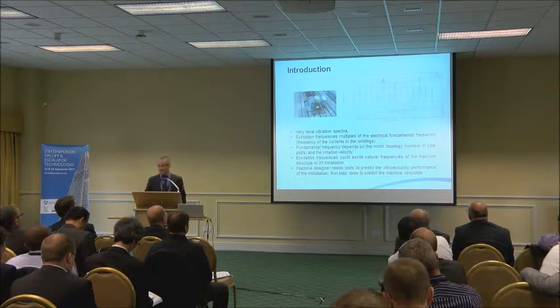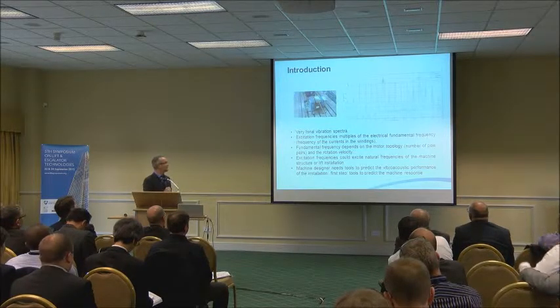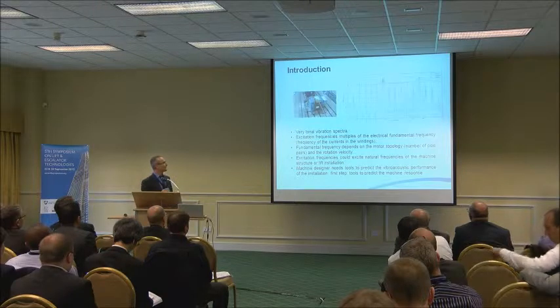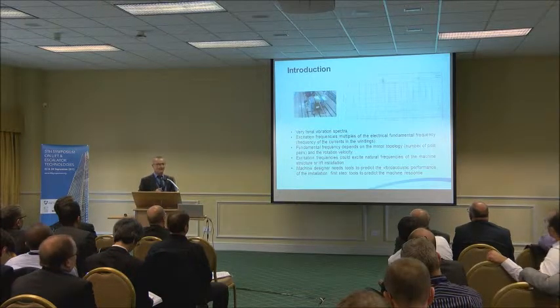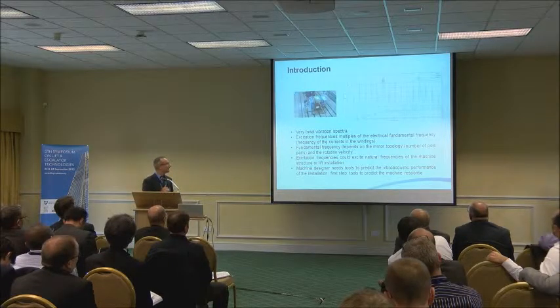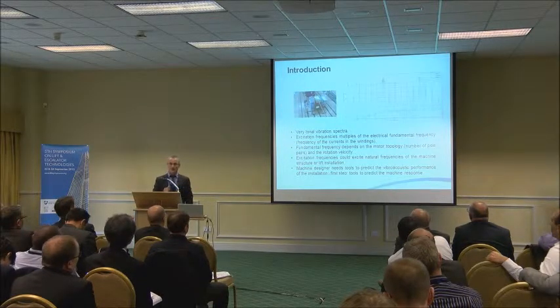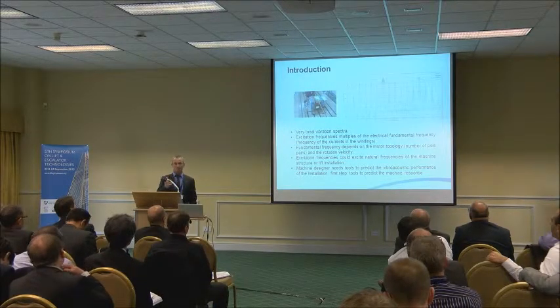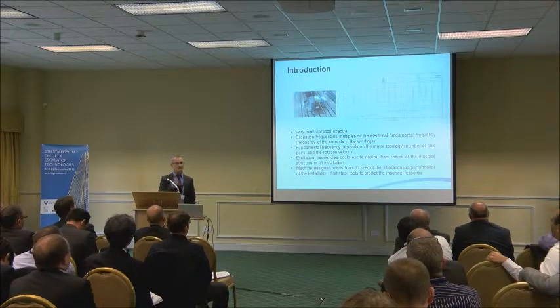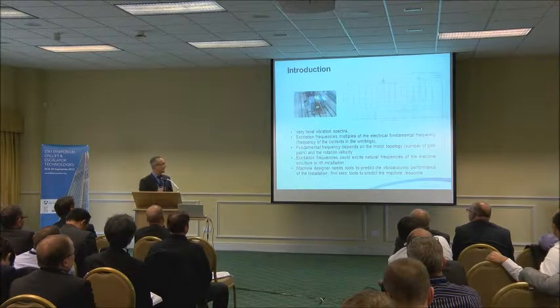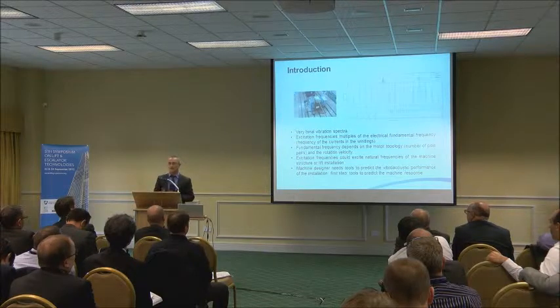Let us give a brief summary on vibrations caused by the machine. The spectra due to machines is very tonal. We have very manifest peaks that are multiples of the fundamental frequency. The fundamental frequency is the rotation frequency of the machine.